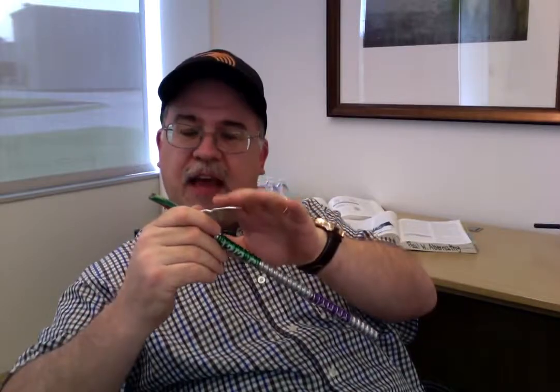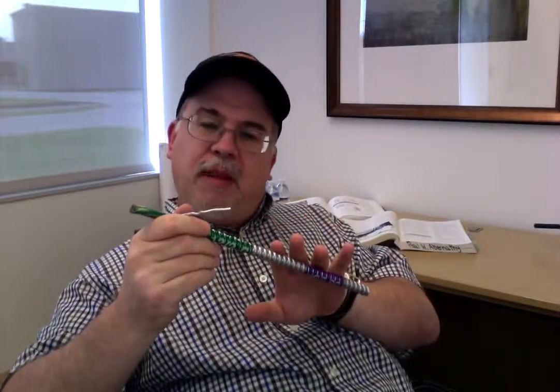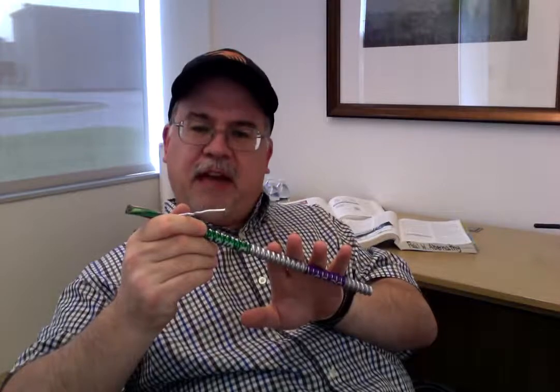Now, what does that say? If you have your code book, pull it out and look at it. But what that basically says is, for those circuits that are going to be feeding branch circuits inside of patient care spaces or areas, the actual armor itself or the raceway has to be considered an equipment grounding conductor. And of course, with the SmartGround product, we know that it is because of this 10 gauge aluminum bonding/grounding conductor in contact with the armor, and because the National Electrical Code under 250.118(10)(b) says that it is. So we know that we meet the requirements of the first part of that 517.13(A).